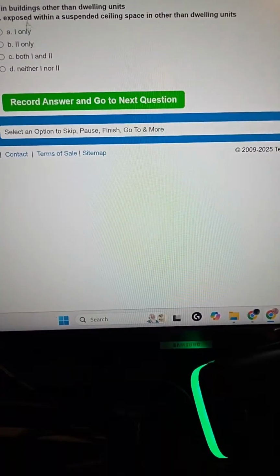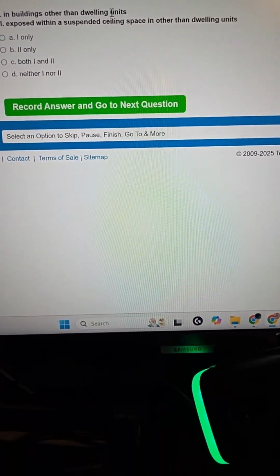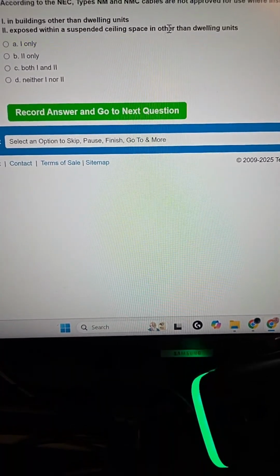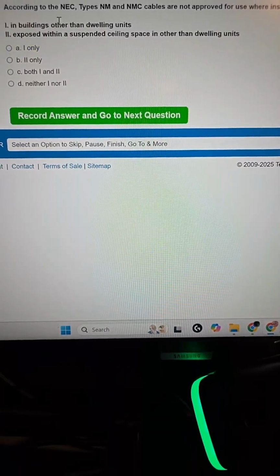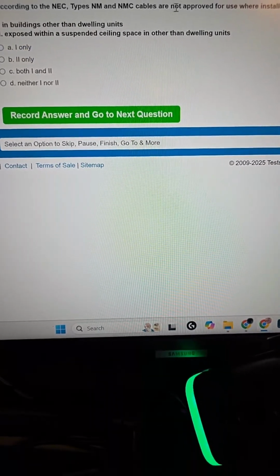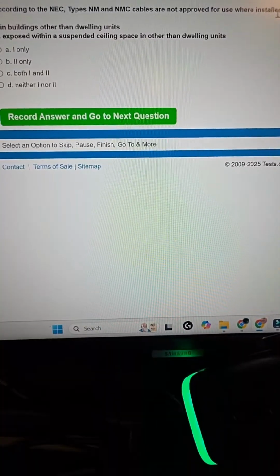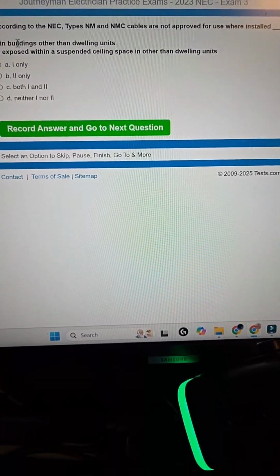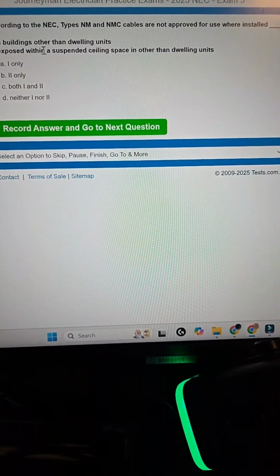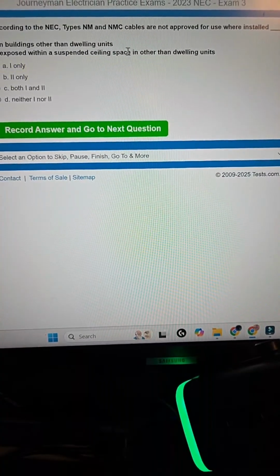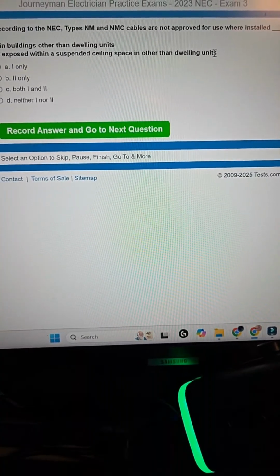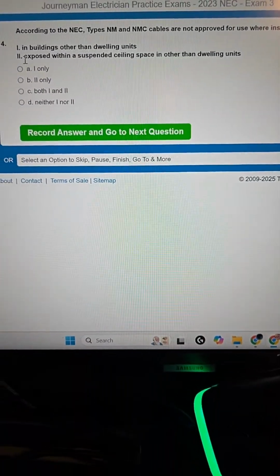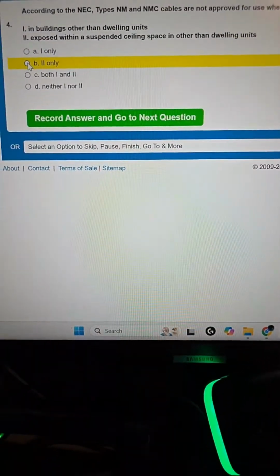Next. In buildings other than dwelling units, exposed within a suspended ceiling space other than dwelling units. Okay, so NM and NMC are not approved for use where installed exposed within a suspended ceiling space in other than dwelling units. So it's going to be 2 only. But we can look that up.